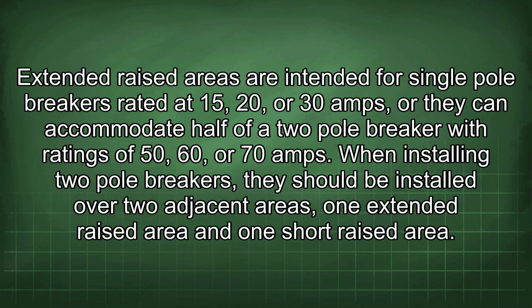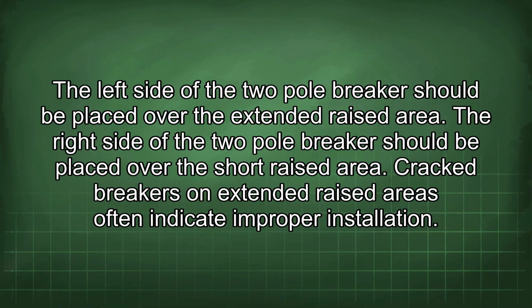When installing two-pole breakers, they should be installed over two adjacent areas, one extended raised area and one short raised area. The left side of the two-pole breaker should be placed over the extended raised area. The right side of the two-pole breaker should be placed over the short raised area.